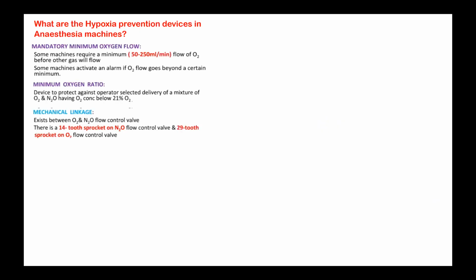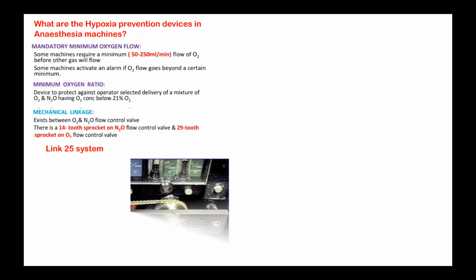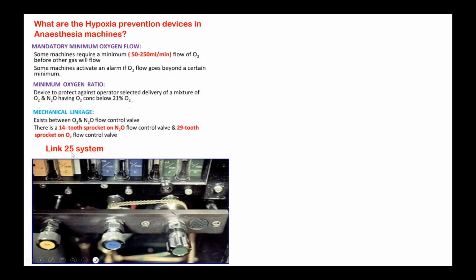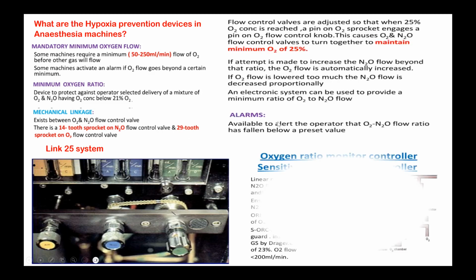Hypoxic prevention devices in anesthesia machine: minimum mandatory oxygen flow, minimum oxygen ratio, and mechanical linkage. This is called the Link-25 system. How does it work? Can you see a chain going around? 14 sprockets for nitrous oxide and 29 for oxygen. So this is how we always get a 2:1 ratio. That is how it is controlled.